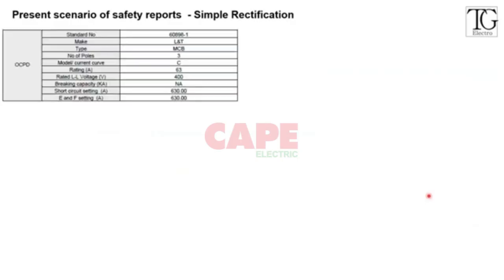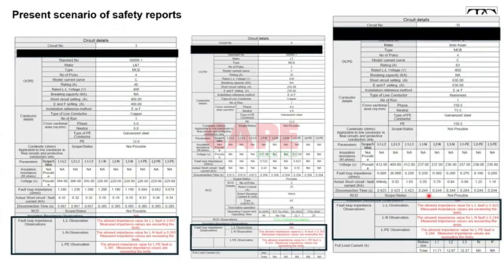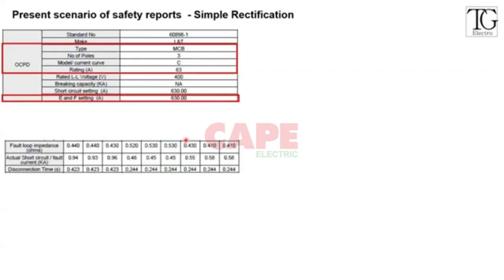Now, there are other things also. For example, in the previous one I showed a whole report. Now I'll show you one report and how to rectify this error. First we have to see the protective devices. They have given an L&T make MCB of 63 amps, C type. And obviously the fault current for C type is going to be 10 times, so it is 630 amps.